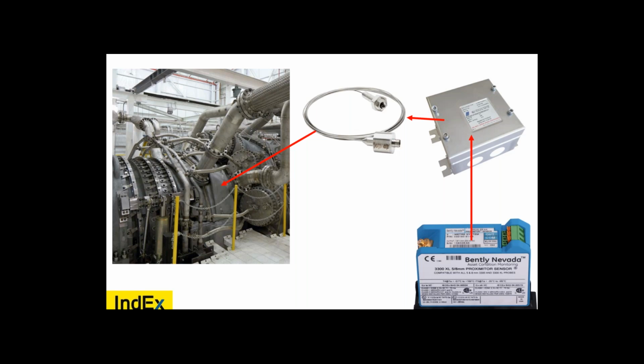Is there a protection technique that does not have to have EX components inside? EX p and d are 2 of 3 that do not need to have EX certified equipment inside. We spoke about the other one today. Will this be available on YouTube? Yes. This is a very difficult standard because it has changed significantly.